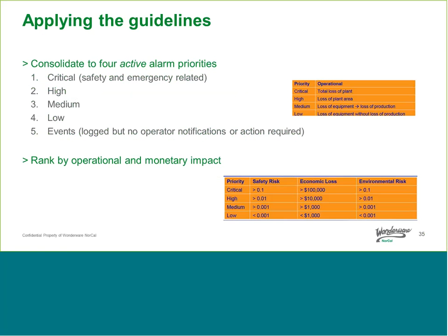And if we look at best practices guidelines for alarm management, really you can categorize your alarms into 4 priorities: critical, safety and emergency related, high, medium, and low. And so the events could be another type of alarm priority, and events don't need operator visibility or operator action. The event just might be that an operator logged in or changed a set point, and you want to log that event. But nobody needs to be aware of that in real time. So you can rank these 4 alarm priorities, critical, high, medium, and low, by safety risk, by economic loss, or by environmental risk. So once you categorize your alarms, you can apply them to the Wonderware SCADA system.